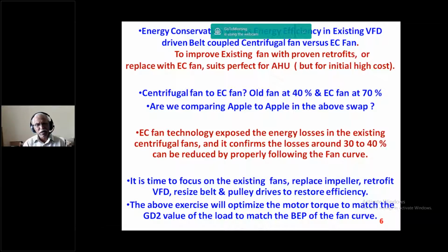But here we are not comparing apple to apple. With EC fans, electronically commutated fans, instead of a 15 kilowatt, 20 HP fan, they will have 4 fans maintaining almost the same duty. It is a cascaded efficiency of the fan. Four sets of EC fans are operating in place of one single fan. That is the new concept that is coming up. But a typical Indian always thinks about what can be done to improve the existing system. So the EC fan has in fact exposed the energy losses on the existing centrifugal fans, and these losses are around 30 to 40%.